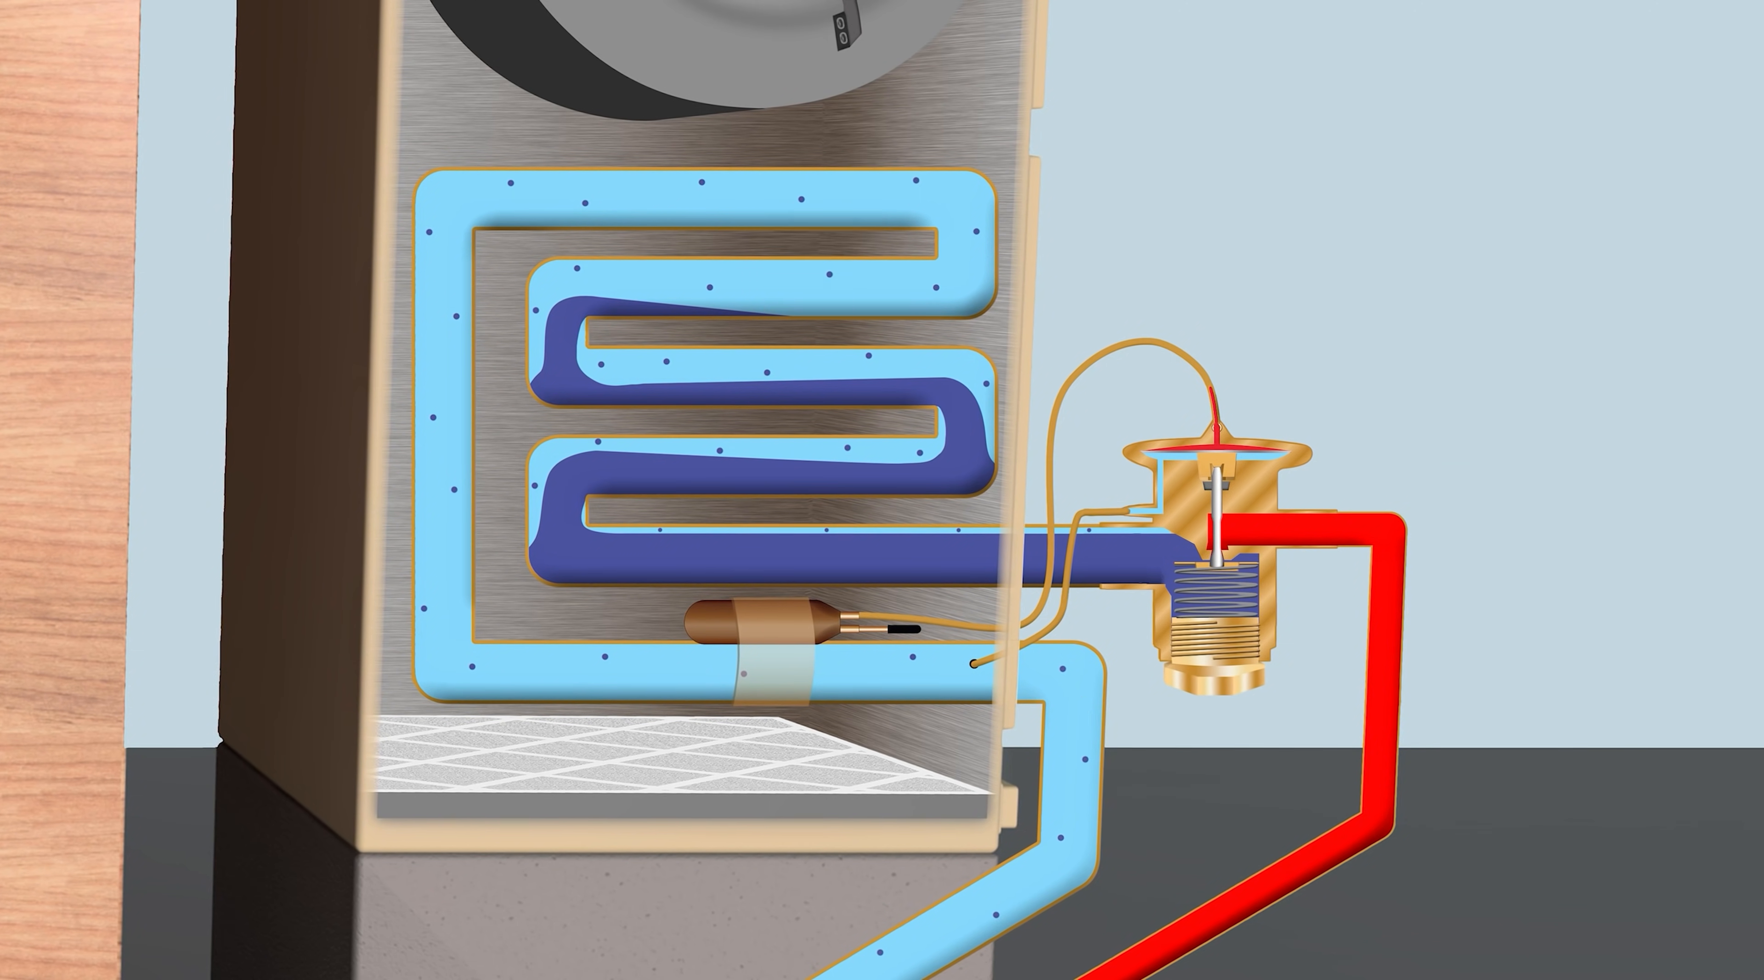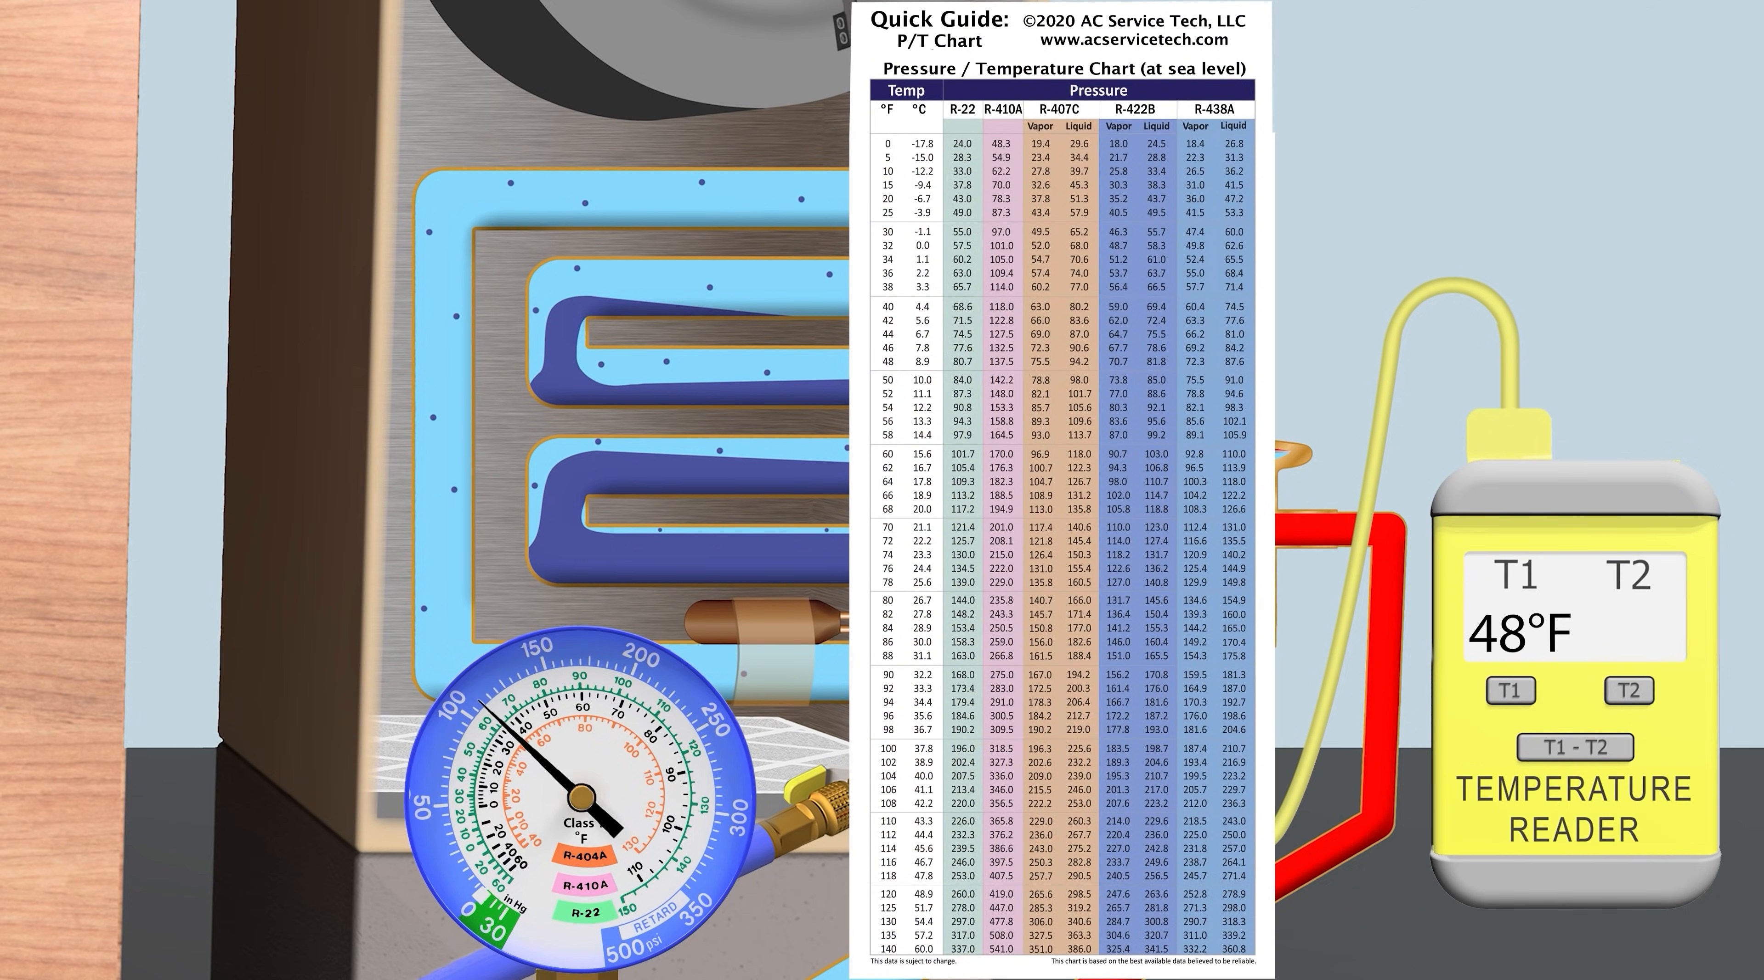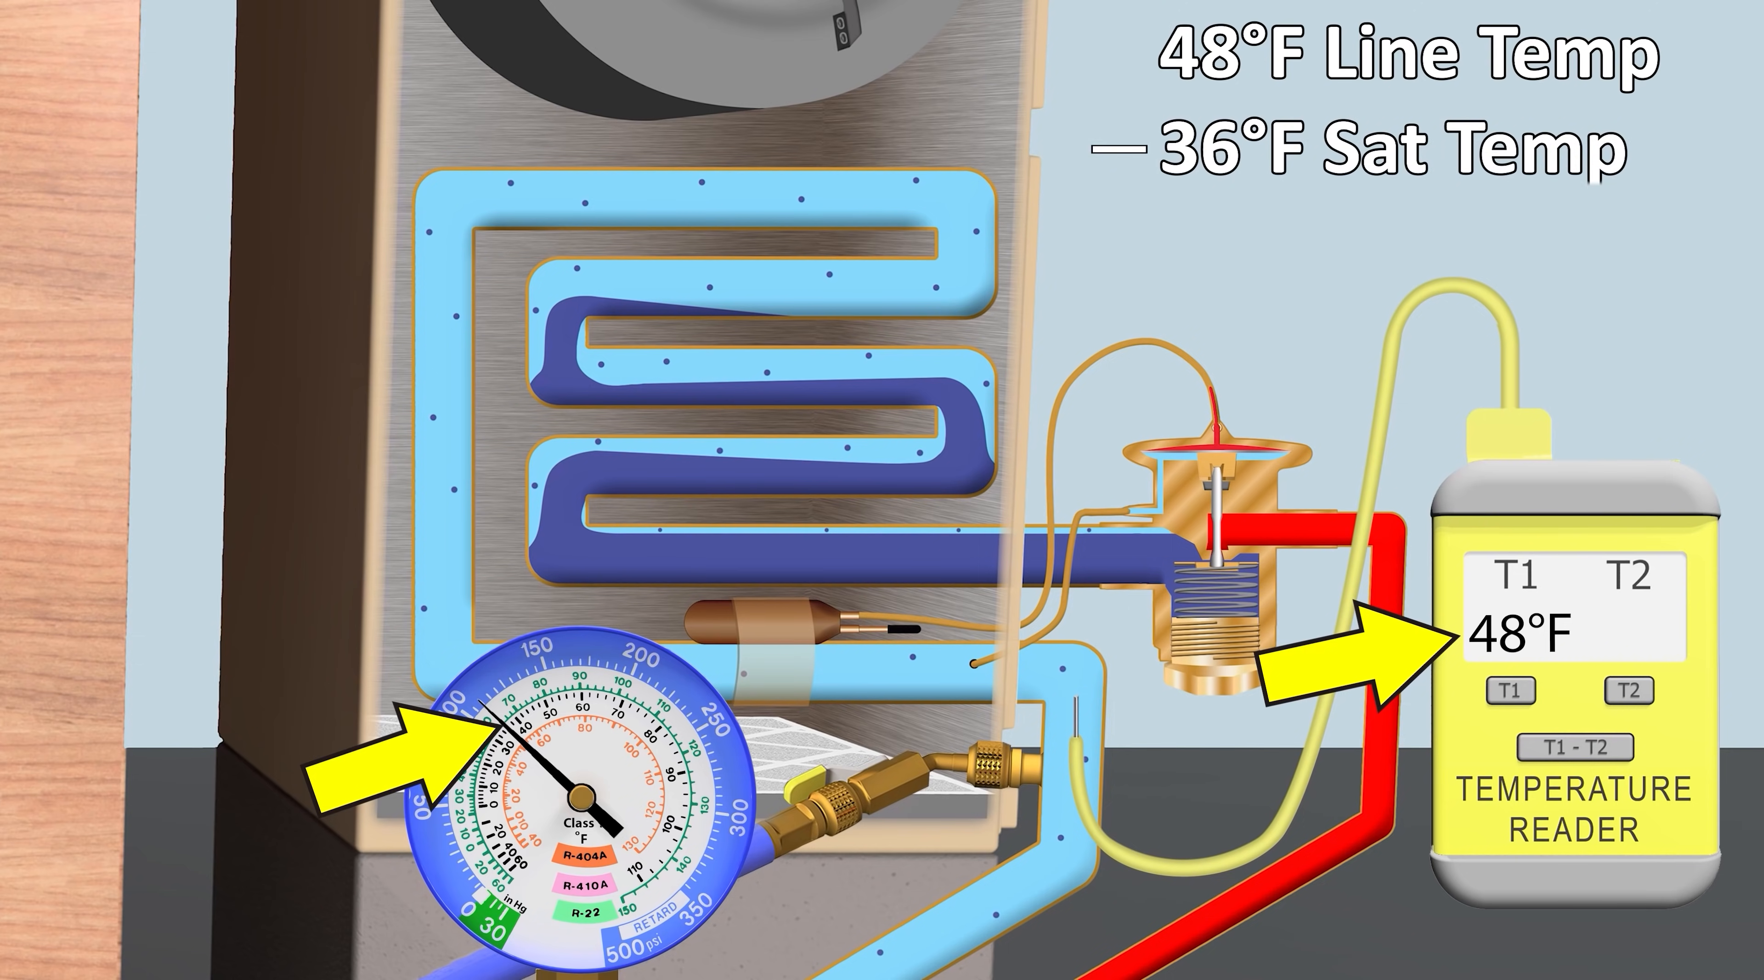When you're measuring superheat, you need a pressure tap on the vapor line and a temperature on the vapor line. You take that temperature, which in this case is 48 degrees on this line, and you take a pressure reading on the vapor line. In this case it's 109.4 psi, and that converts to an R410A saturated temperature of 36 degrees. So you take a vapor line temp of 48 minus a saturated temperature of 36, and you're left with 12 degrees of superheat.